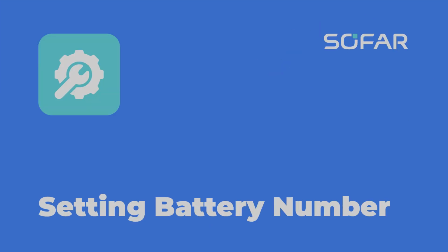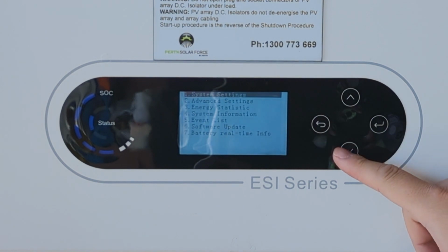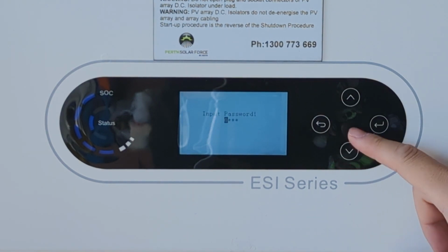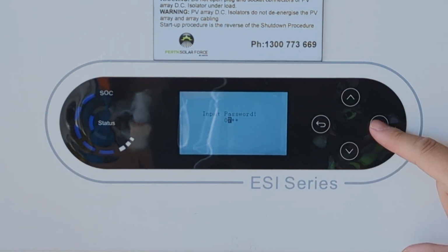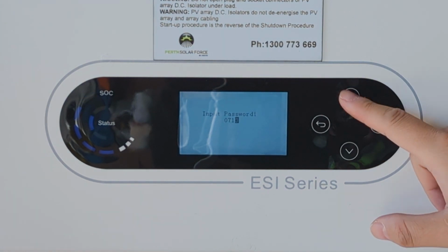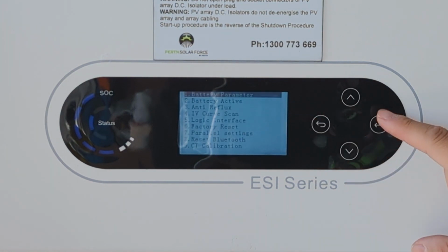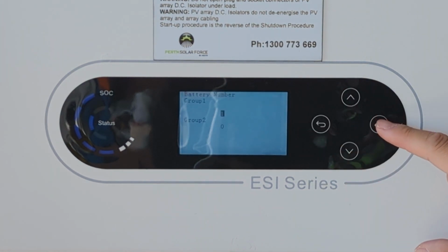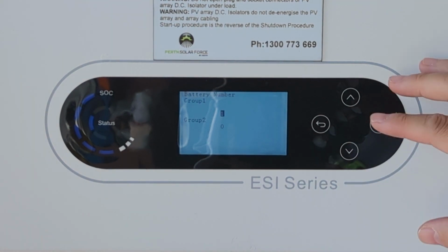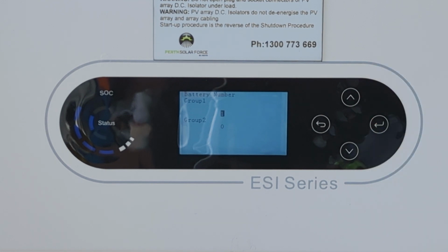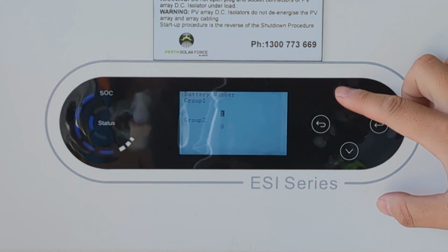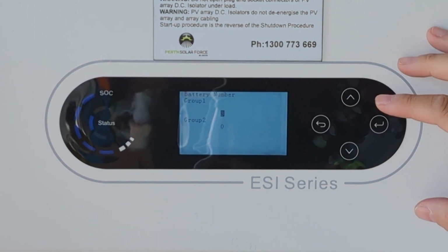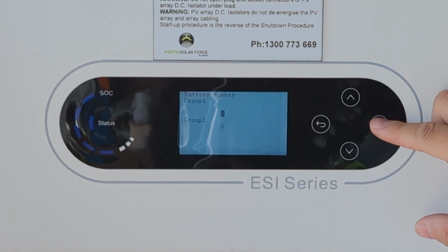Next, we set the battery number. Select the option System Settings, then Advanced Settings. Enter the password 0715. Select the option Battery Parameter, then Battery Number. Group 1 is for the batteries under the inverter, up to 3. Group 2 is for the additional batteries, up to 3. This installation is 15 kilowatt hours, so the battery number is 3.